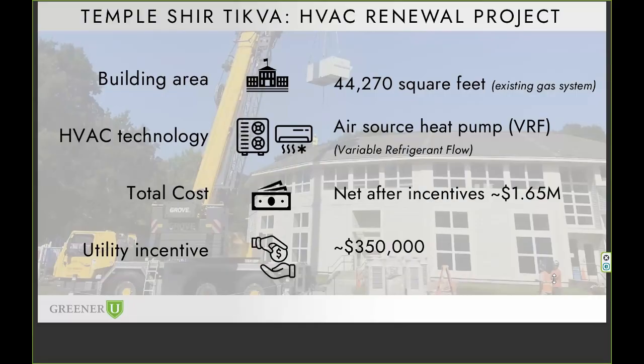The eventually selected technology was an air source heat pump, or a system called VRF, variable refrigerant flow. So it's a form of air source heat pump, and that became the primary heating source. They did retain a small portion of natural gas heating with the boiler system, partly for peak loading and partly for backup. But they've managed to reduce about 85% of their total natural gas usage with the new system.